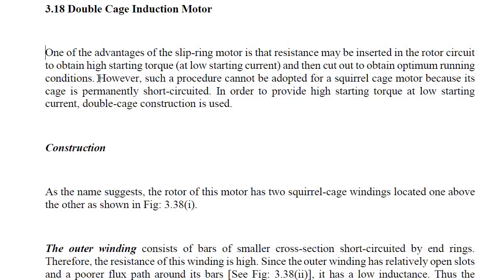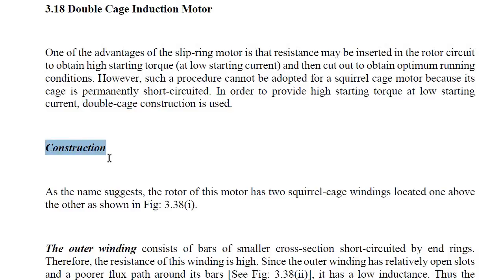However, such a procedure cannot be adopted for the squirrel cage motor because its cage is permanently short circuited. So, in order to provide high starting torque at low starting current, double cage type construction is used. In the squirrel cage induction machine, there is no chance of adding resistance in the rotor circuit because the bars are short circuited at the ends by end rings. That is why we use double cage type construction in the squirrel cage motor.